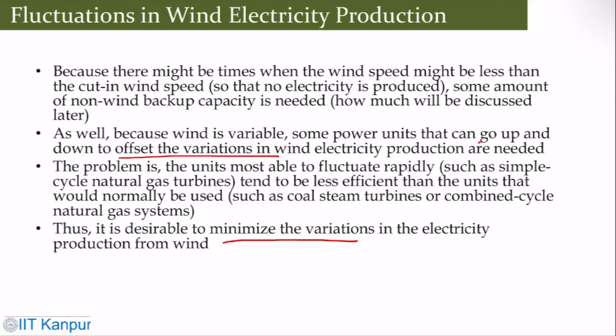This variation or fluctuation can be addressed by minimizing the rapid second-to-minute fluctuations in wind output. Use of variable speed turbines provides some smoothing of output at a time scale of seconds. Together, several turbines in a wind farm provide some cancellation of fluctuation at a time scale up to a minute. One can also implement short-term storage of excess energy: flywheels, supercapacitors, flywheel hybrids, and a two-way connection to the grid. So this is the short-term mitigation strategy for fluctuations from seconds to minutes.